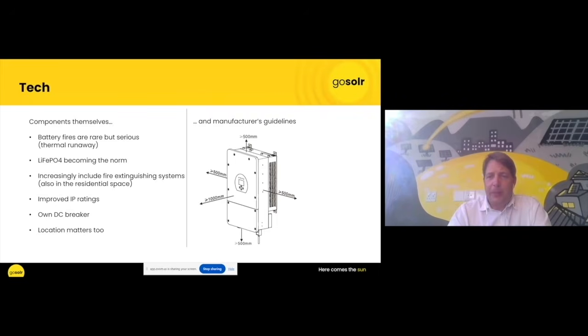But again, we mustn't forget about the people side of things. Manufacturers, when they release components, it comes with a document, an installation manual. And if we look at this, it's quite standard that you need to have space between the inverter and the ceiling, inverter and the batteries, on the side of the inverter or in front of it. And this is to make sure that heat dissipation is not impaired and that you don't create a risk of having a roof catching fire because the inverter is too close to the roof or too close to flammable material.